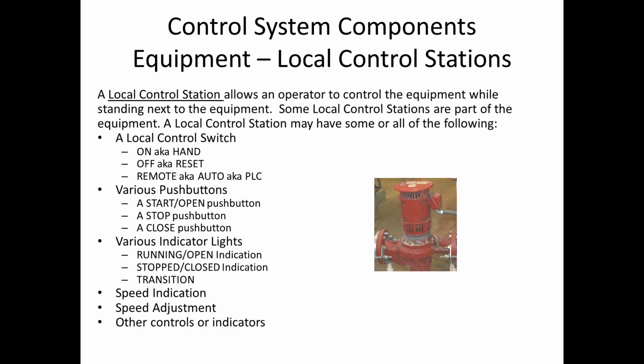There are opened and closed lights on a lot of valves, and sometimes when those are both lit up, that tells you that the valve is neither open nor closed, that it's somewhere in between. It may be in transition, or it may have been stopped in the middle of the travel because you didn't need it either fully opened or fully closed, just a little bit.